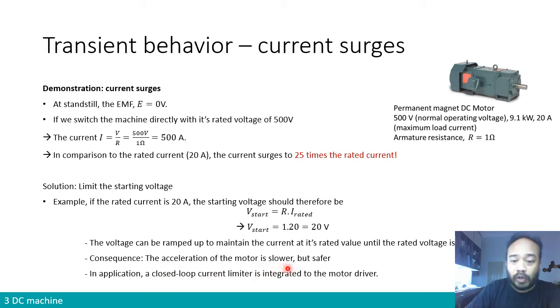The acceleration will be slower, but it will be much safer, and you will keep your motor for a longer time. The life duration of your motor will be longer because it will not experience the thermal stress of having the current too high inside the machine. In real industrial applications, you will not start your machine manually by starting with 20 volt and then ramping up the voltage little by little.